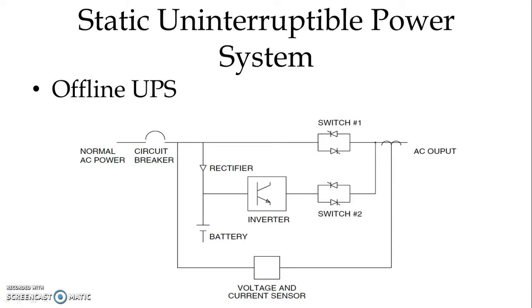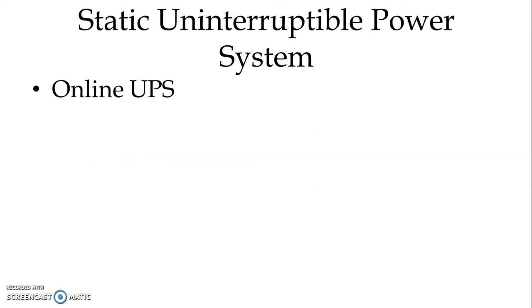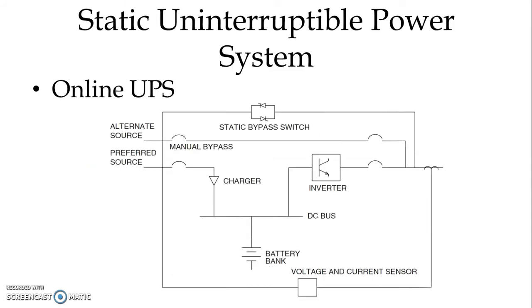So as we discussed, in the static UPS system, we do not have any rotating part, and that is why the switchover must be possible within half of a cycle, and then we'll be having a continuous supply to the critical load. Same way we have online UPS.